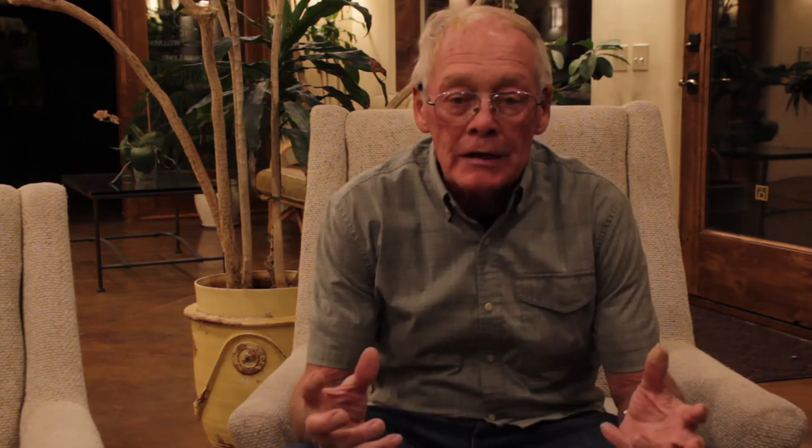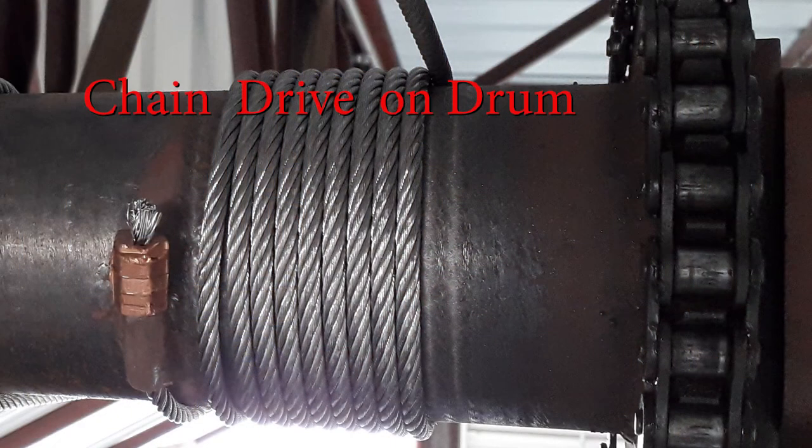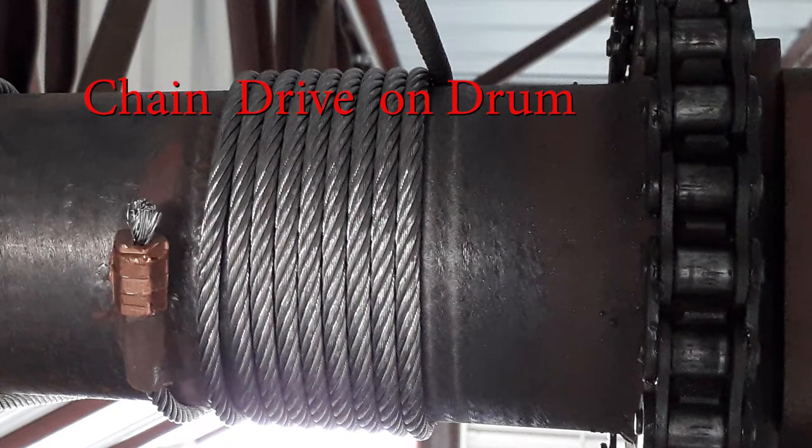Now we need to move into the actual drive mechanism itself. These particular doors within the green hangars have a top drive system, which is opposite of some of the Wilson doors that have the drive system down at the bottom. There are basically three parts to that system: one is the large drum to which the cables are attached, which also has a tooth system that engages a large chain to a transmission. From the transmission there's a large pulley with a rubber belt that goes to the smaller pulley on the electric motor. So the three components are the drum, the electric motor, and the transmission.